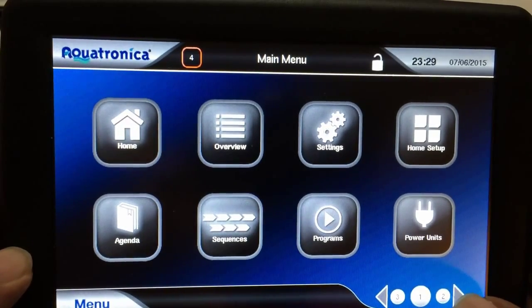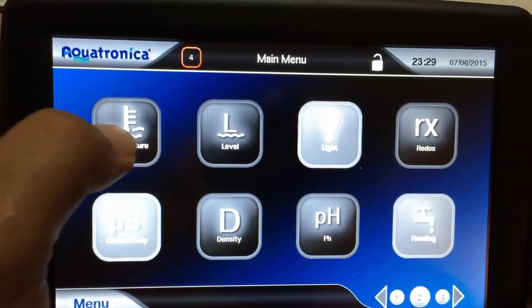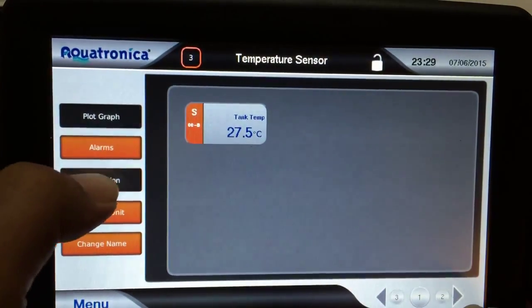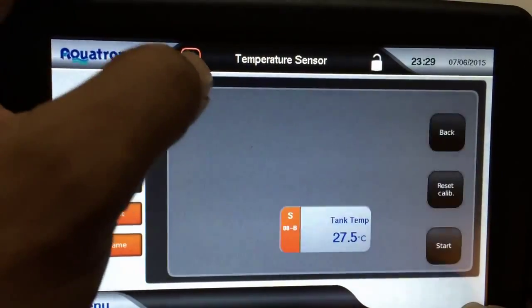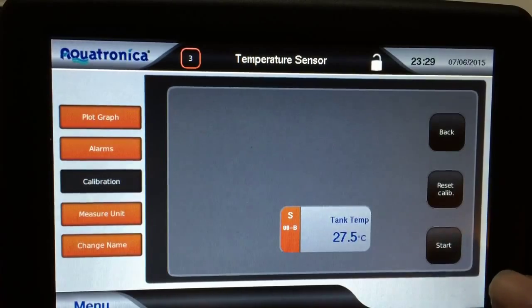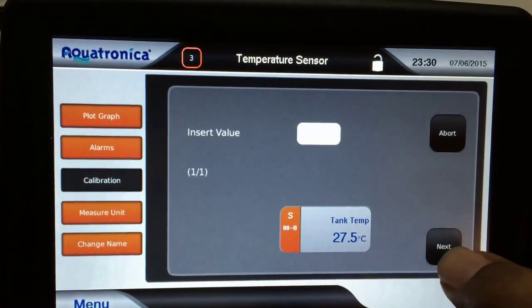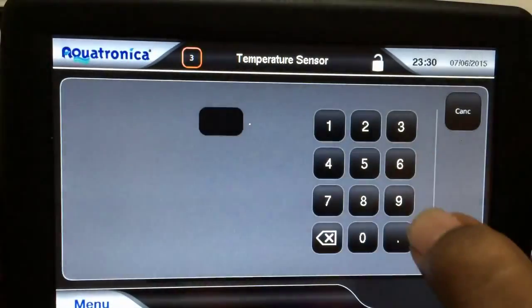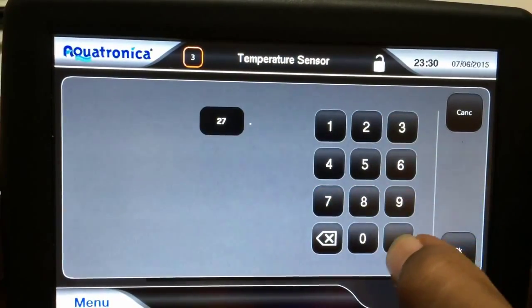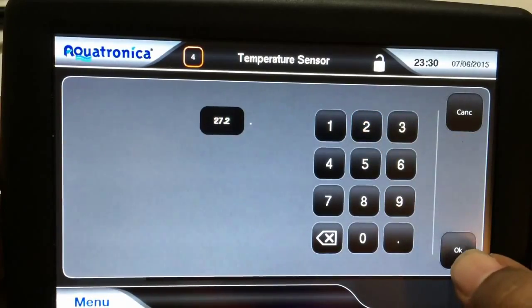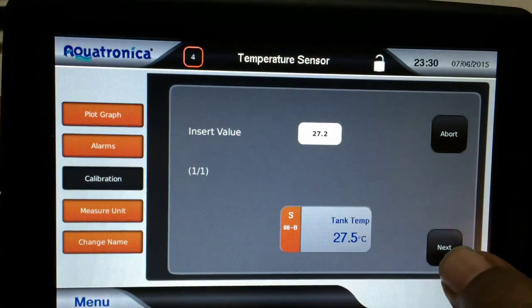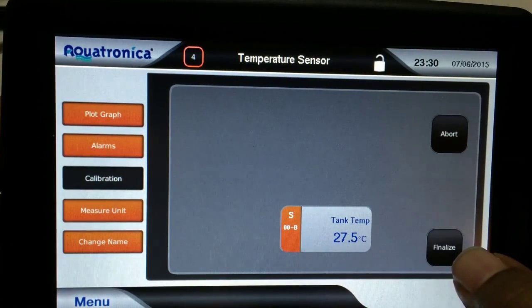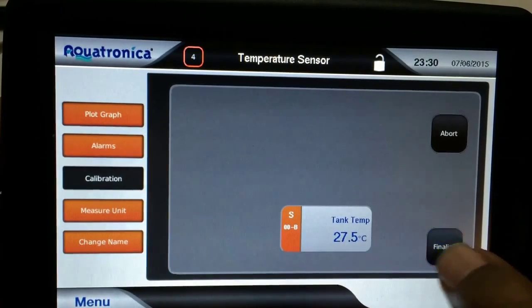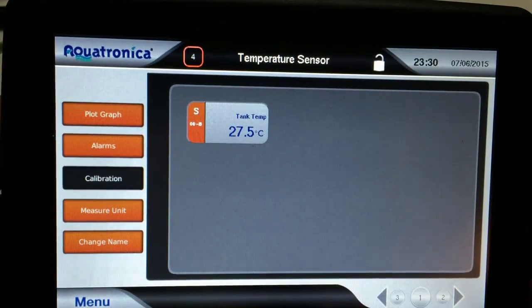So I would go into menu, go over to temperature, go to calibration, select which of the temperature probes. I only have one. Start, and I'm going to put in 27.2, and I'm going to press OK and press next, and then finalize. And I guess it takes a little time for it to adjust.